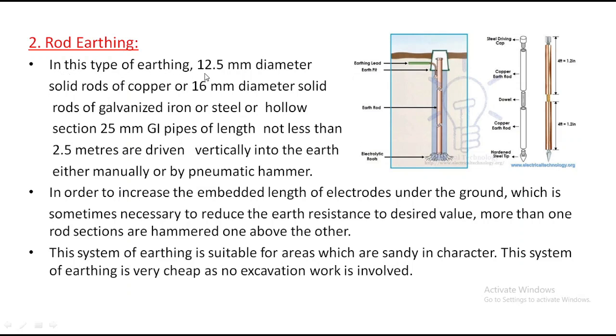In this type of earthing, 12.5 mm diameter solid rods are used for copper and 16 mm diameter solid rods for galvanized iron. So for copper it is always less, and for galvanized iron or steel it is more. Or hollow section 25 mm GI pipes of length not less than 2.5 meters. If it is hollow, then you have to use 25 mm. Hollow means there is a space in the rod. They are driven vertically into the earth either manually or with a pneumatic hammer. This is the vertical model.